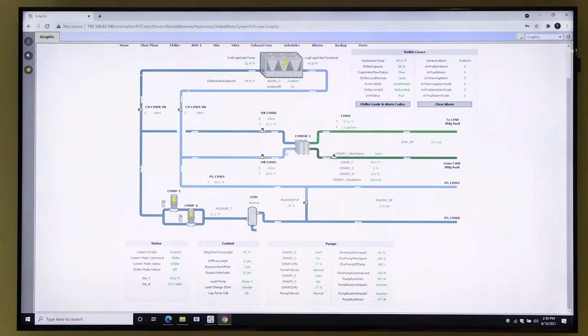Once we've proven that these valves are open, we're going to close the isolation valves to the chiller, so you won't have flow to the chiller when we're just going to the heat exchanger. Okay, you'll be isolated up above from those valves. Yeah, thank you.